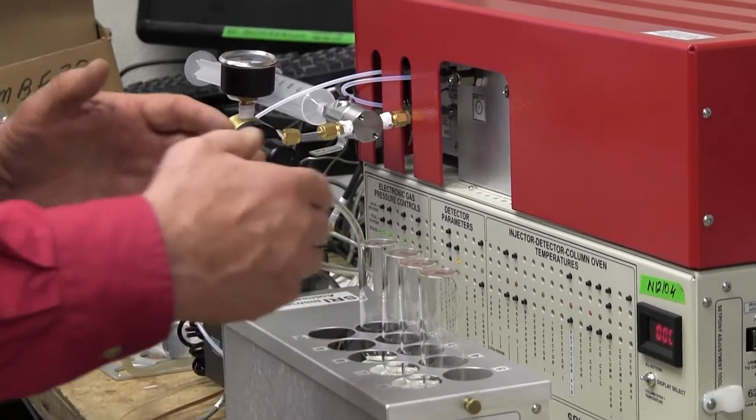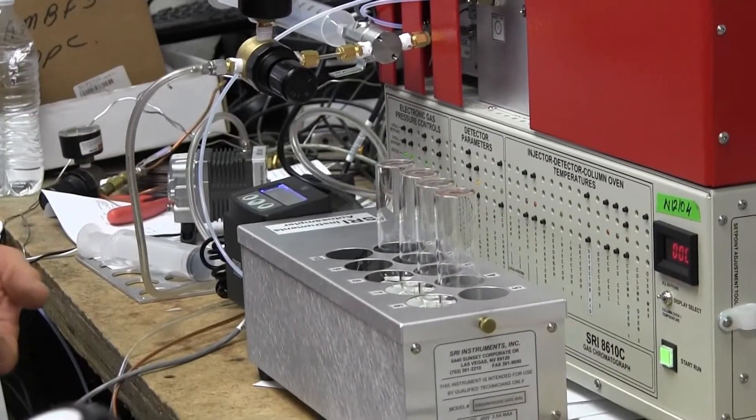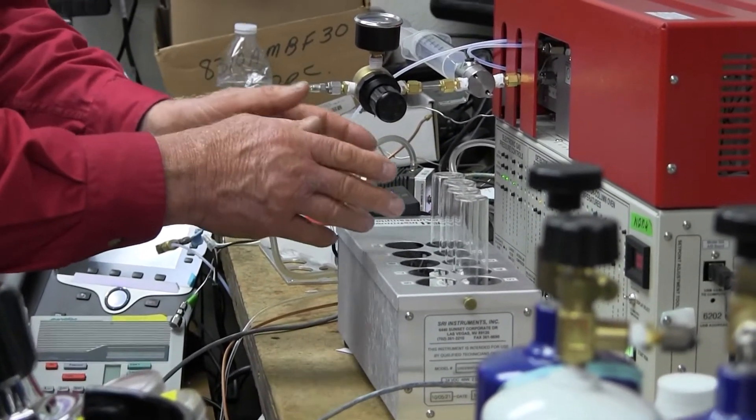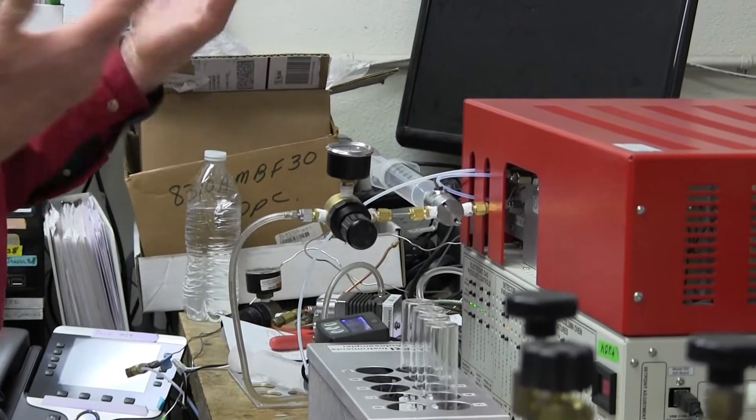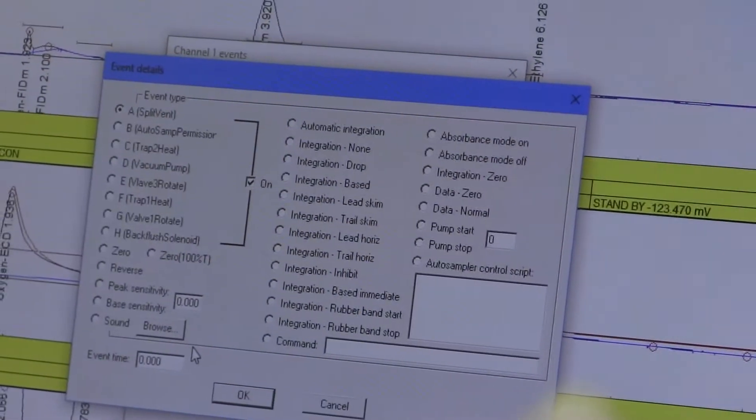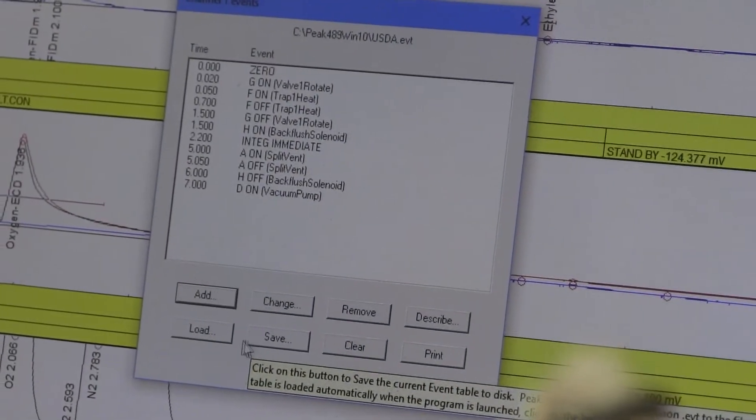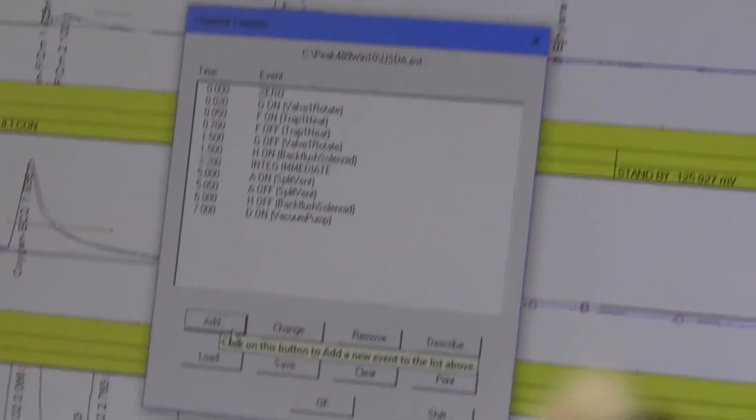And then turn relay D off because what that does is once you've positioned the selector to a particular vial, you need to pressurize the vial. And then you need to release the pressure through the loop. And that's how you get the sample out of the vial. And then subsequently in the analysis, you do this maybe ten more times. Pressure release, pressure release. Once the injection is made, it really doesn't matter. It just goes through and then out. It doesn't do anything to the GC. So you can do this event as many times as you want. So you'd go back to that event table and you'd put in a time. I'm just going to pick a time of seven minutes. So at seven minutes, you'd turn relay D on and that would turn on the pressure to pressurize the vial. And then let's say you determined by trial and error that a tenth of a minute, six seconds, was plenty of time to do that. So you'd put in another event at 7.1 minutes where you'd turn relay D off.